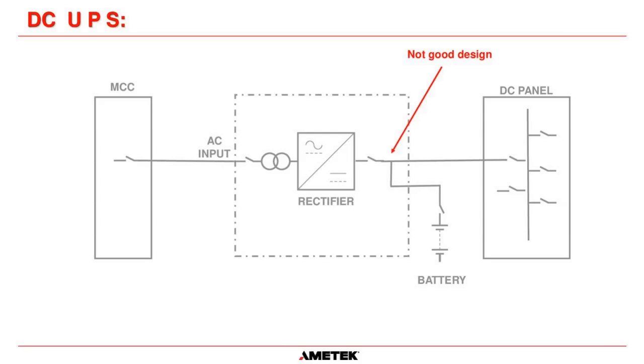Now, in this system here, what the plant has done, and I've actually seen this in person on a few examples, is this is not a good design. What they actually did is this tie point here is actually the output terminals of the charger. And the output terminals of the chargers are usually a bolted connection onto a bus bar. In AMETEK SCI chargers they are. And what they do is they put two sets of cables on that tie point, which is a convenient point to connect both your battery and your load cables.